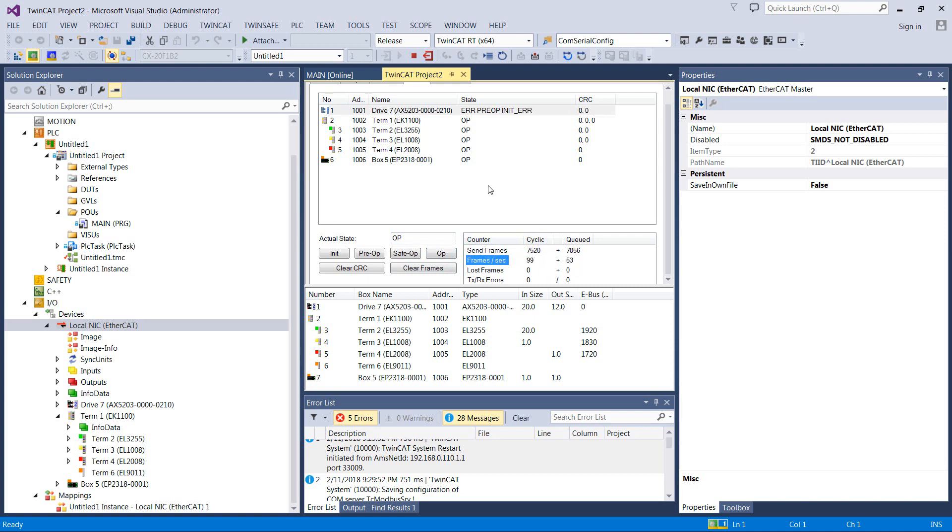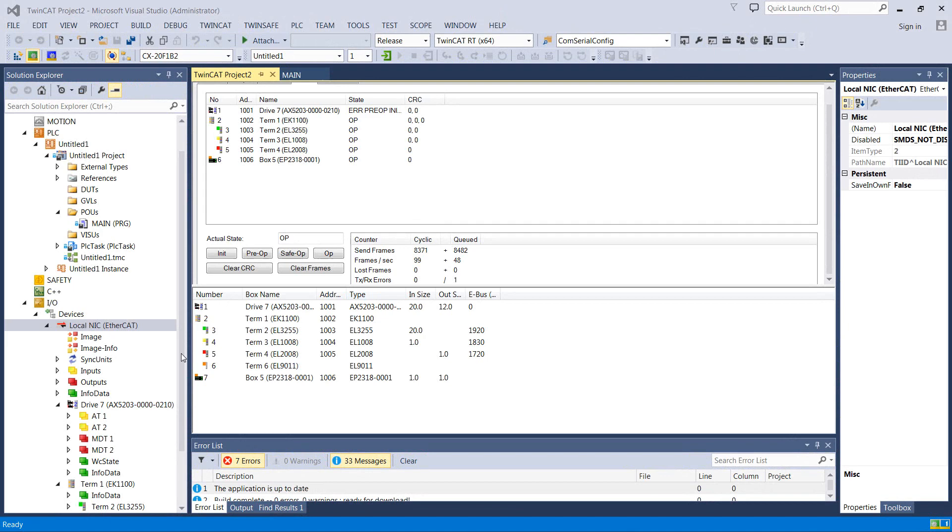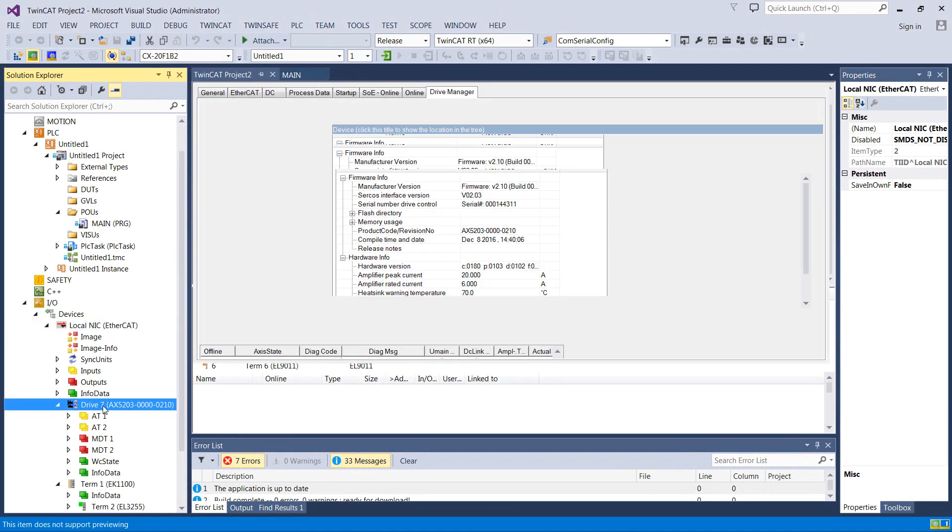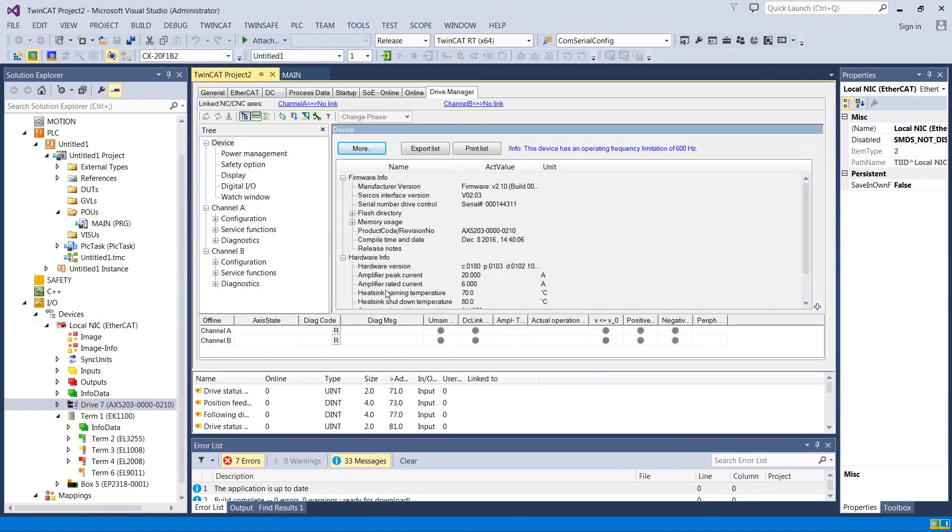So if you have something that says something like error, pre-op, init, we need to go find out what's going on with that device. Okay, so to inspect this drive, we'd come over to this entry in the tree over here, open it up.